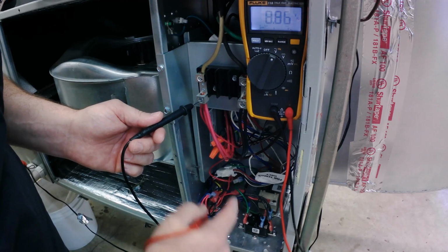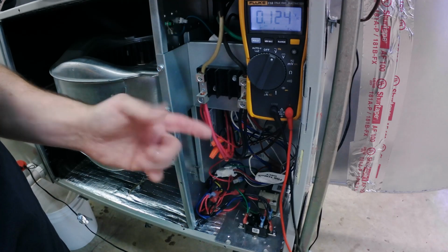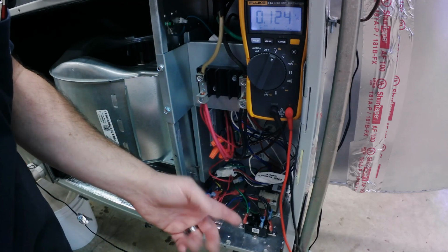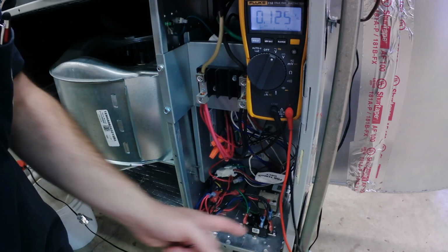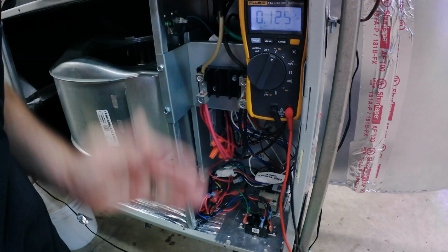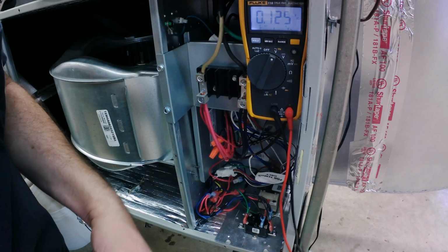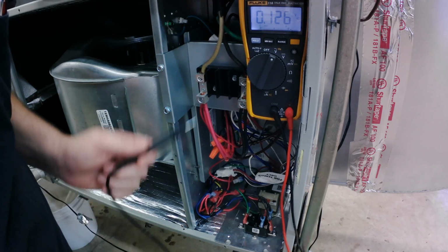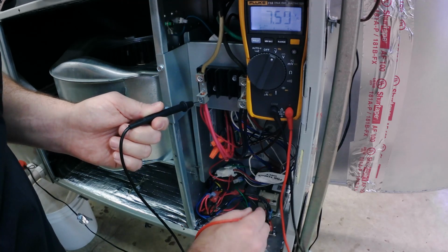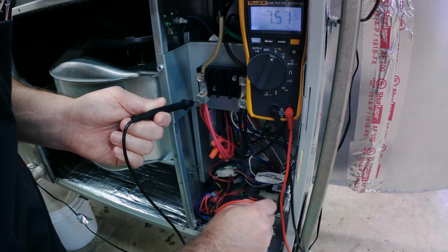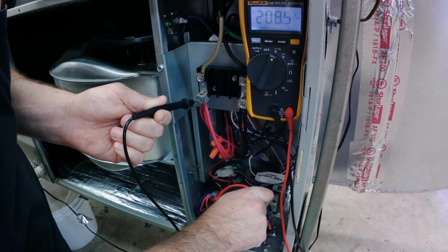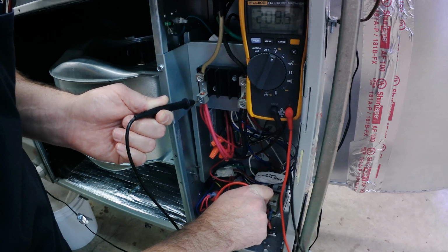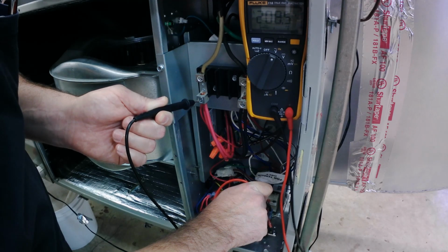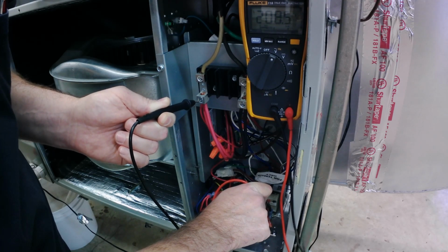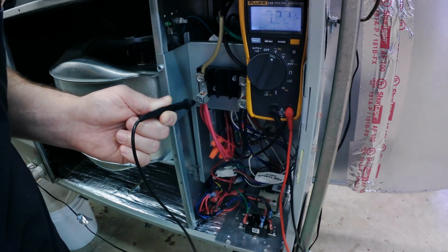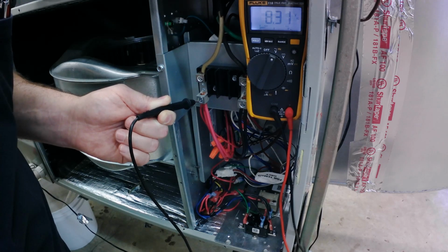So what I'm going to do is, I know that on a relay, since the switch breaks one side of power, on this fan relay, not a 2-pole contactor, but on this fan relay specifically, I'm going to have L1 coming in, and that switch is going to break that contact, and L1 is going to eventually go out to turn the fan motor on. So I'm going to keep one lead on L2, and I'm going to reference L1, right? And you can see here, I've got my 208 power source, my total voltage. A lot of guys dig in me on this, right? But I know I'm seeing my total voltage, so I know that I've got power sitting at that relay. I also know that L1 is only half that voltage, L2 is the other half, right?